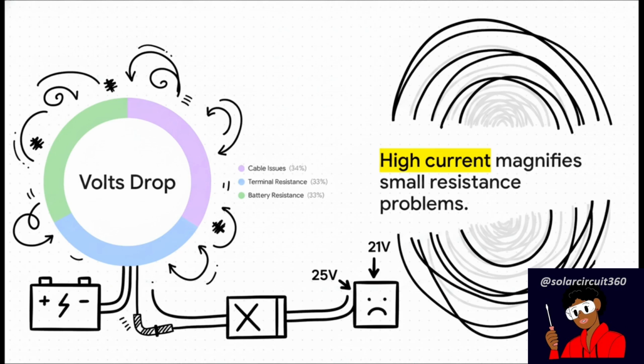Any of these can create substantial voltage loss before the power even reaches the inverter. Higher current literally causes larger voltage losses through your connections. So your battery might be pumping out a healthy 25 volts, but thanks to some corroded cable lugs or a super long cable run, the inverter might only be seeing, say, 21 volts. The inverter sees that massive drop, thinks the battery is dead, and triggers the shutdown to save itself.